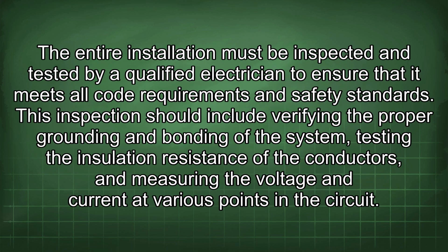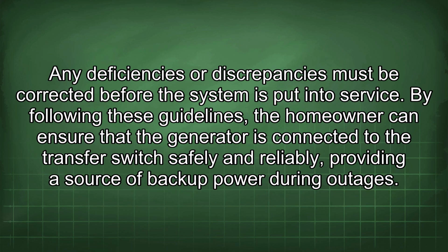The entire installation must be inspected and tested by a qualified electrician to ensure that it meets all code requirements and safety standards. This inspection should include verifying the proper grounding and bonding of the system, testing the insulation resistance of the conductors, and measuring the voltage and current at various points in the circuit. Any deficiencies or discrepancies must be corrected before the system is put into service.